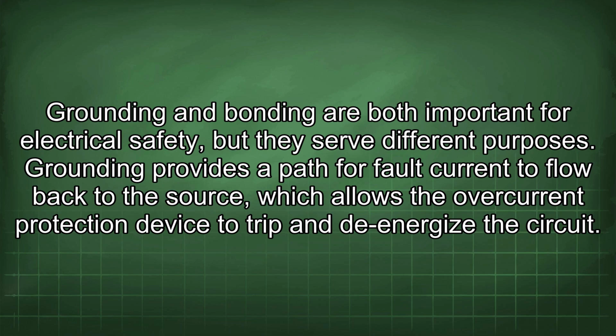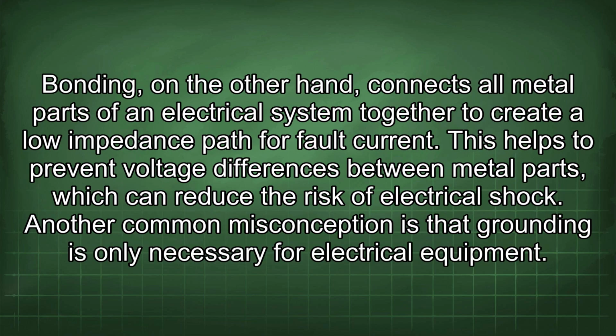Grounding provides a path for fault current to flow back to the source, which allows the overcurrent protection device to trip and de-energize the circuit. Bonding, on the other hand, connects all metal parts of an electrical system together to create a low impedance path for fault current. This helps to prevent voltage differences between metal parts, which can reduce the risk of electrical shock.